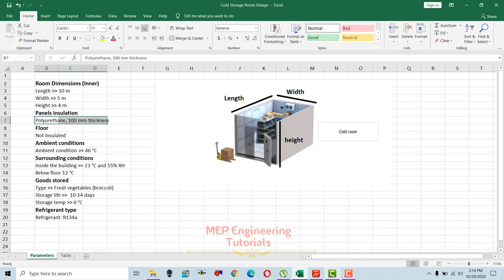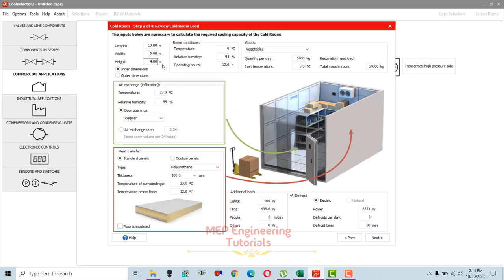The insulation panels used are polyurethane, 100 mm thickness, so select polyurethane and 100 mm thickness. After that, a review screen will pop up where you can review or edit the cold room load parameters. For air exchange, the surrounding temperature is 23 degrees Celsius and 55 percent relative humidity.